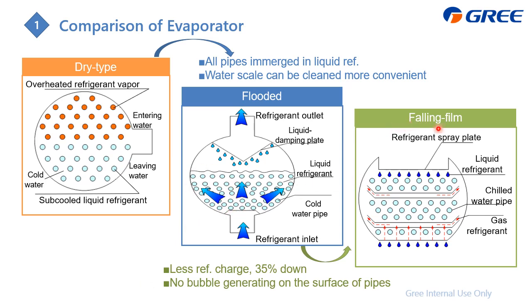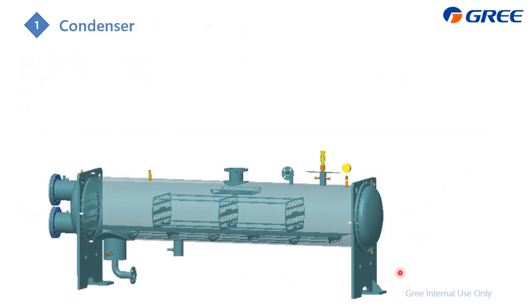And the last is the falling film type, which can save up to, in our case, 35% of the refrigerant amount, and there is also almost no bubble generation on the surface of the pipes. This can raise the heat transfer efficiency. And then later we'll go to the condenser.